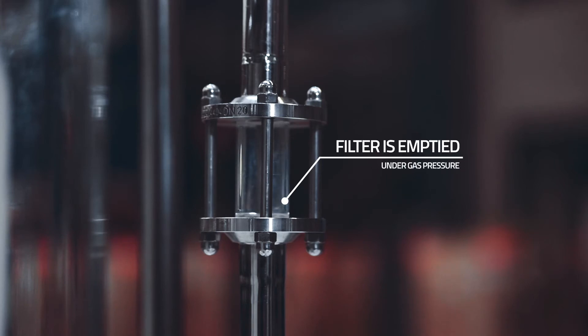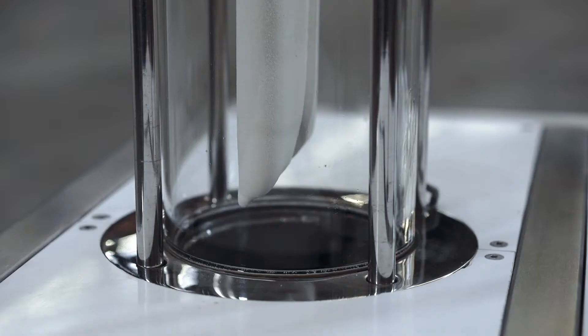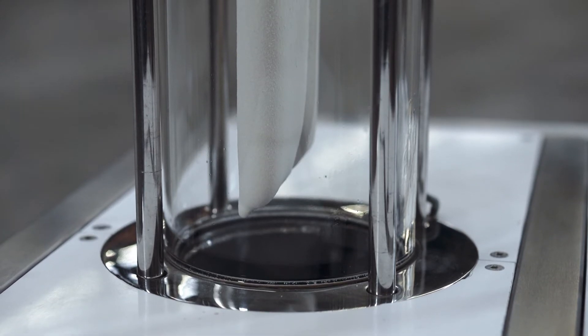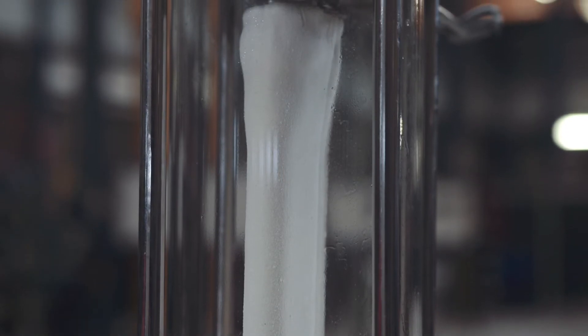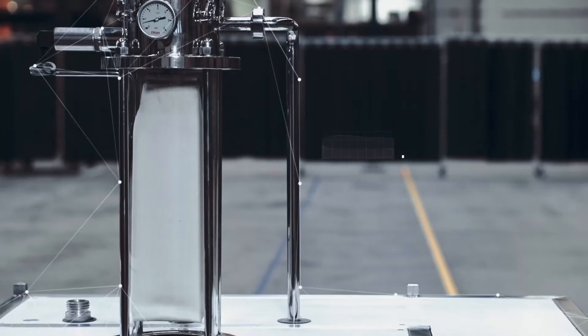After the filtration is stopped, the filter is emptied under gas pressure to keep a positive pressure loss over the filter cake, preventing premature cake discharge. The filter cake is dried for a specific time period using compressed air, nitrogen, or steam to minimize liquid losses and to obtain a dry cake.